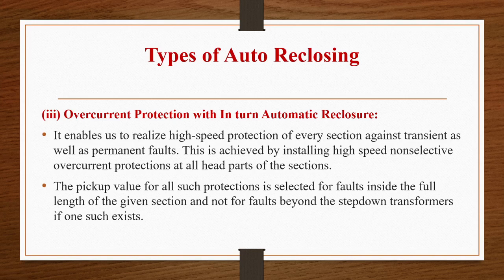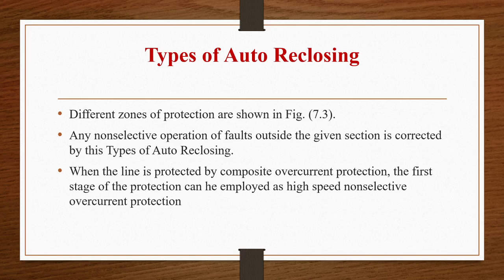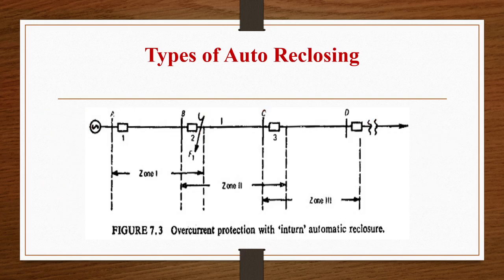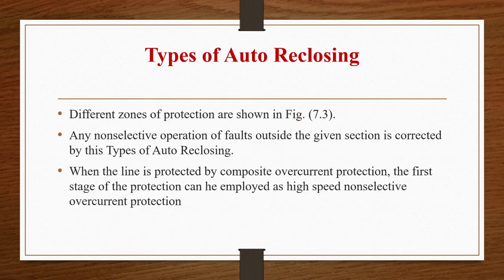So it enables us to realize high speed protection of every section against transient as well as permanent faults. This will be achieved by installing high speed non-selective overcurrent protections at all head parts of the sections. The pickup value for all such protections is selected for faults inside the full length of the given section and not for faults beyond the step down transformers, if such exist. Different zones of protection are shown in figure 7.3. These are the different zones of protection: zone 1, zone 2, zone 3. Any non-selective operation for faults outside the given section is corrected by this type of auto reclosing.